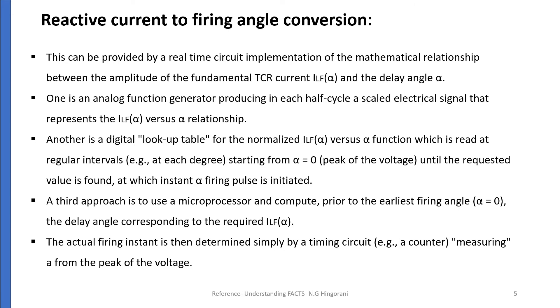Next is reactive current to firing angle conversion. This is provided by real-time circuit implementation of the mathematical relationship between the amplitude of the fundamental TCR current ILF of alpha and the delay angle. We have already studied this mathematical relationship while studying the TCR — that is, the fundamental current equation which is an alpha-dependent quantity. The first approach is an analog function generator producing in each half cycle a scaled electrical signal that represents the ILF of alpha versus alpha relationship.